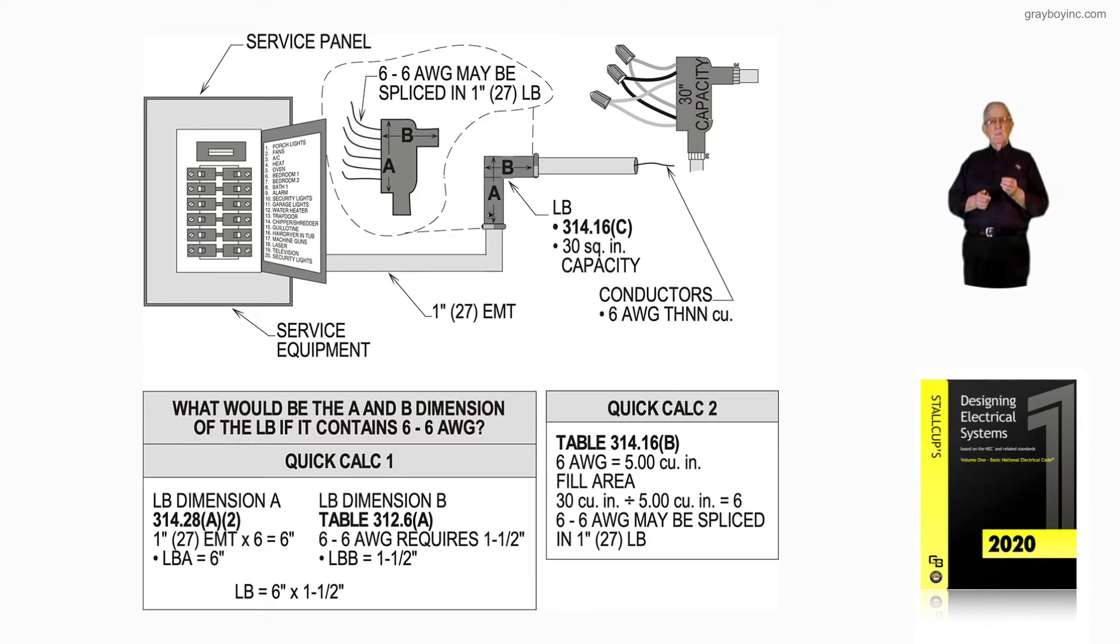The LB dimension B, as you see in the illustration above, would be for six number six AWG conductors would require a one and a half inch LB that we would use there.